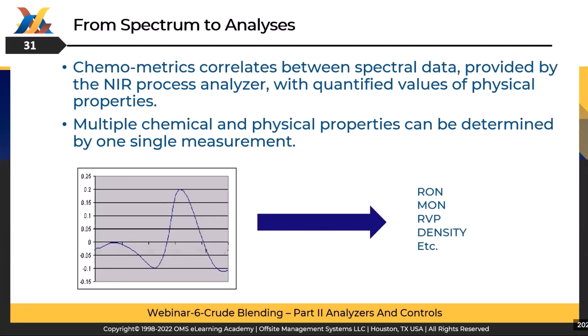Next slide, please. A bit on chemometrics principle and how a mathematical model is built. In order to build a mathematical model, there is a need for spectra. If we're talking about correlative analyzers, we need spectra, and we need laboratory data for these spectra. We're not talking about one single sample, but about 20 or 30 different samples. Once we have spectra and data for them, we can build a calibration model. This happens in the calibration phase. Once we upload the calibration model onto the analyzer itself, each and every new spectrum is multiplied by this calibration model, and this provides us the results of the measurement.